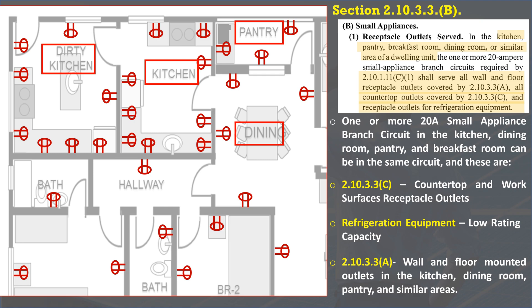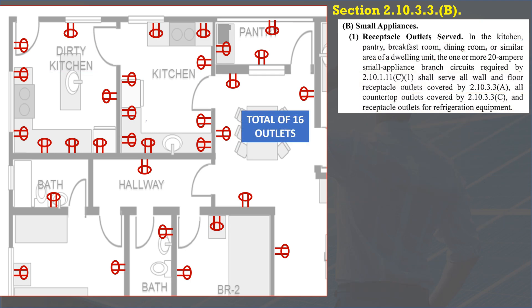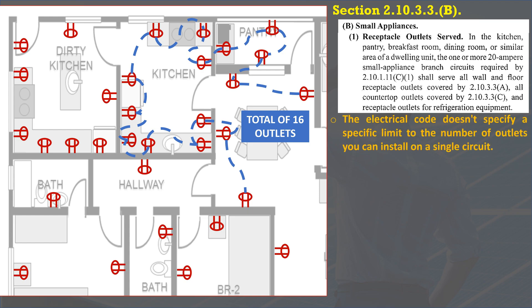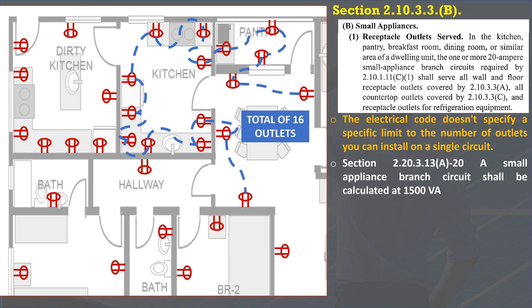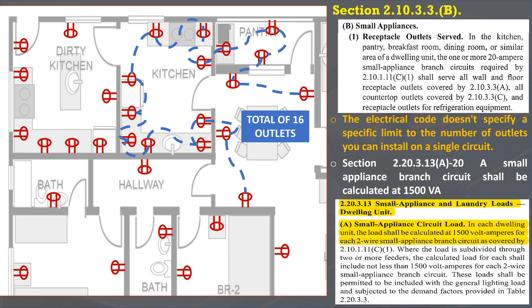Hence, small appliance branch circuits in the kitchen, dining room, pantry, and breakfast room can be in the same circuit. These include countertop receptacle outlets, refrigeration equipment, and wall and floor-mounted receptacle outlets in the kitchen, dining room, pantry, and similar areas. The illustration shows a total of 16 outlets that will be connected to the branch circuit. What are the code rules for the maximum number of outlets per circuit? The electrical code doesn't specify a specific limit to the number of outlets on a single circuit. However, this small appliance branch circuit shall be calculated at 1500 VA as specified in Section 2.20.3.13A.